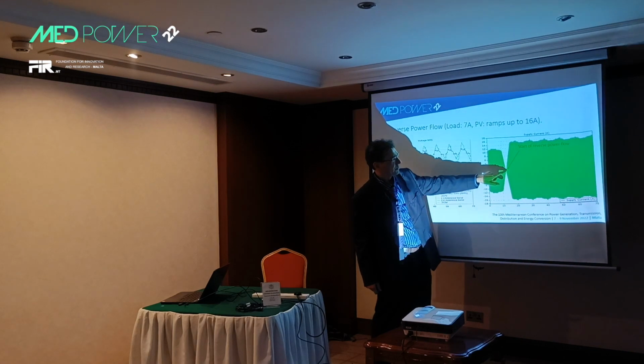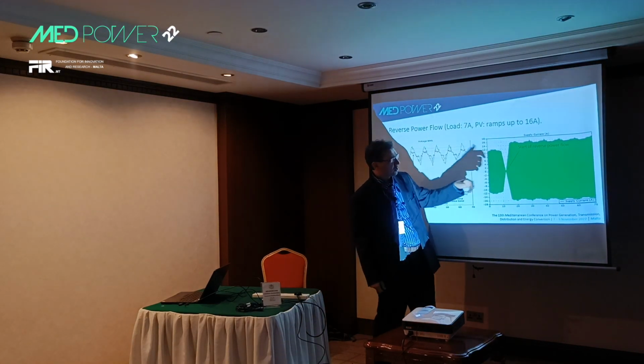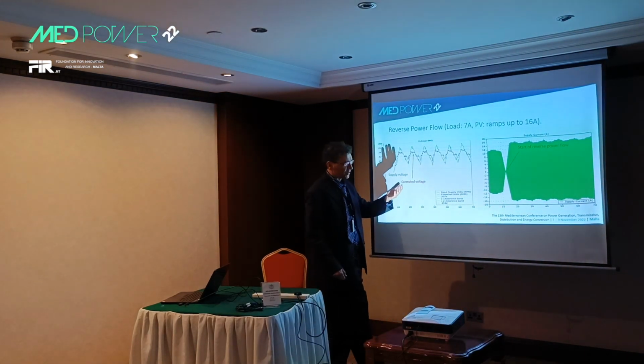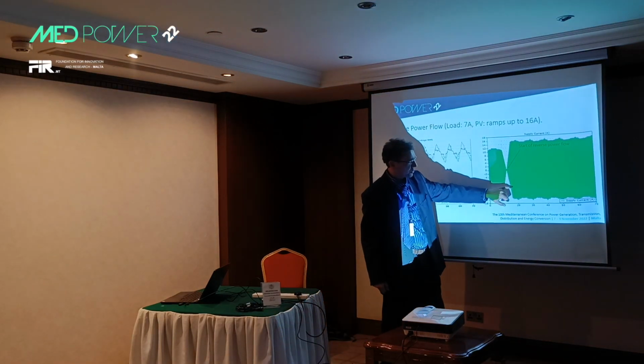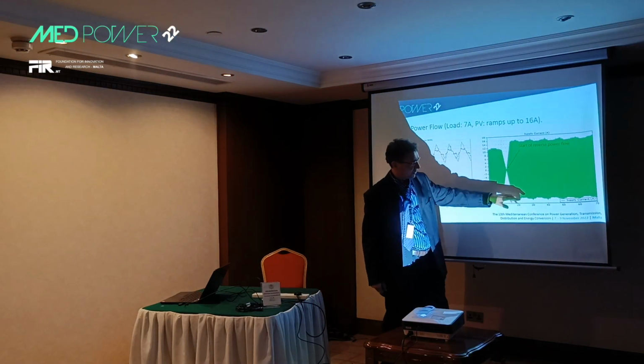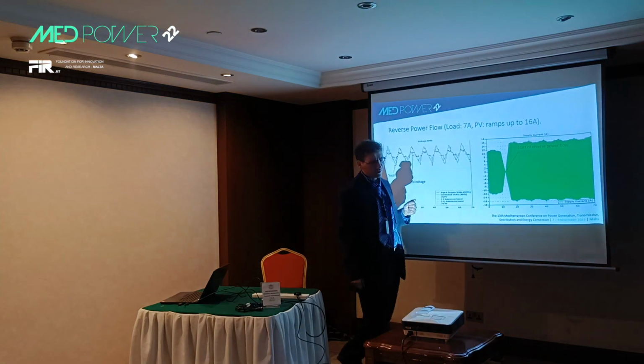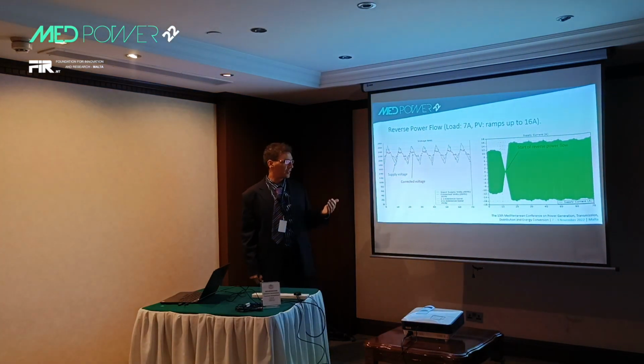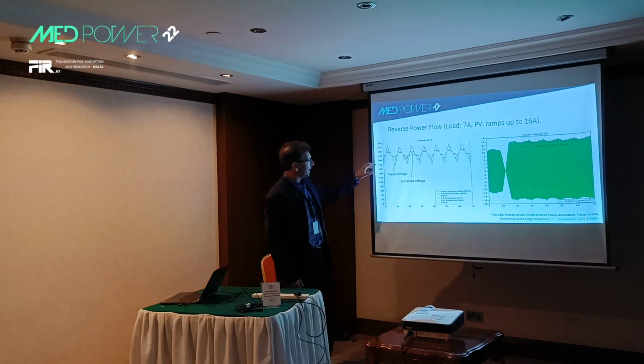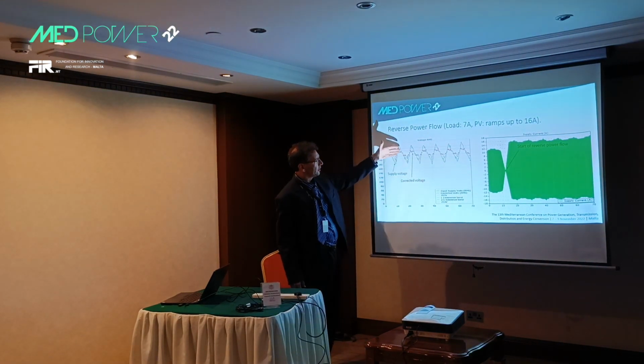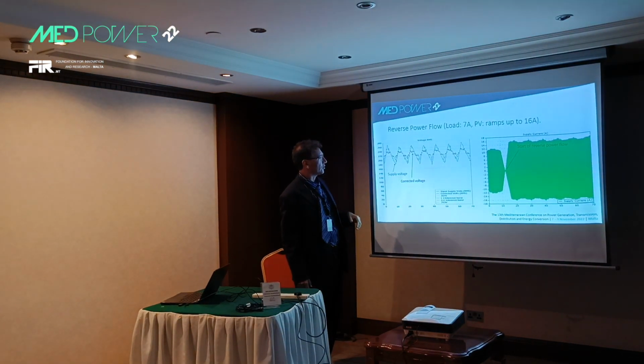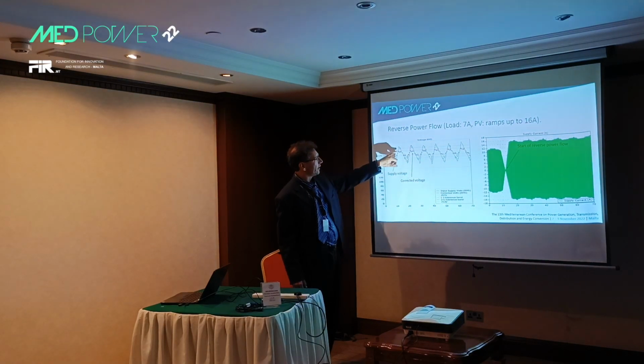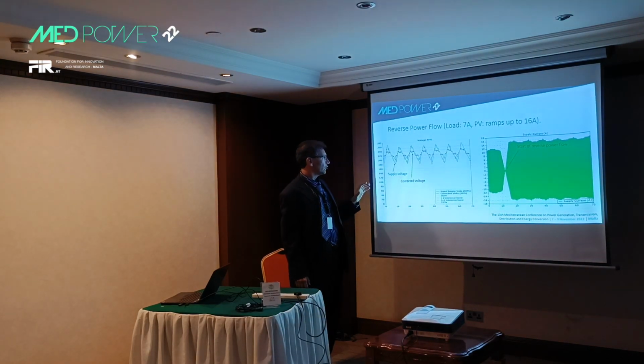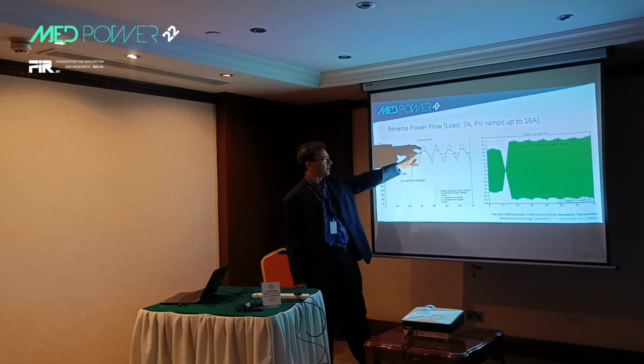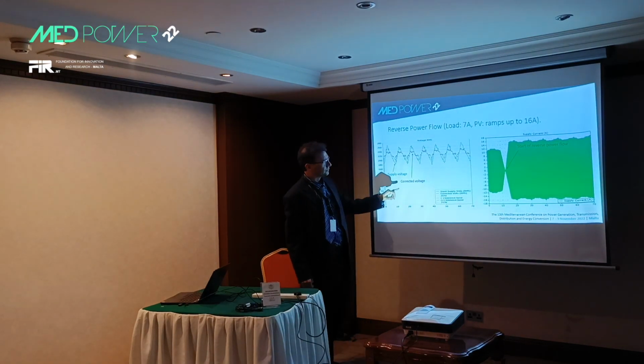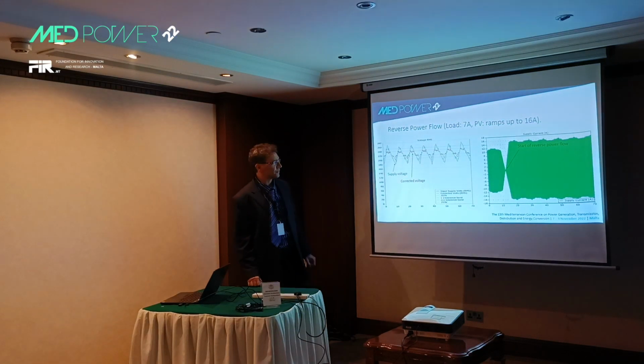At that point, basically the consumer load is completely being supplied by our PV system. As we continue to increase the PV system, all this current is now being pumped back into the grid. Once again, we assume the grid voltage to be distorted, as shown in the green voltage over there, and the controller has managed to a certain extent to control the voltage within the EN 50160 standard.